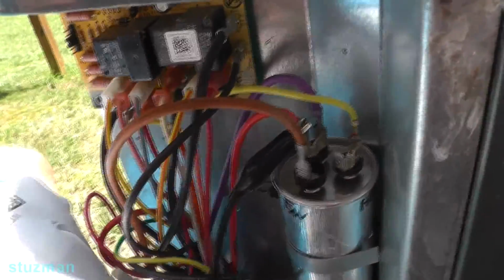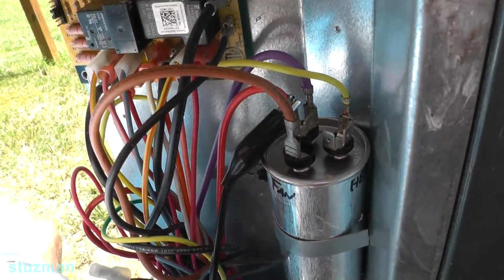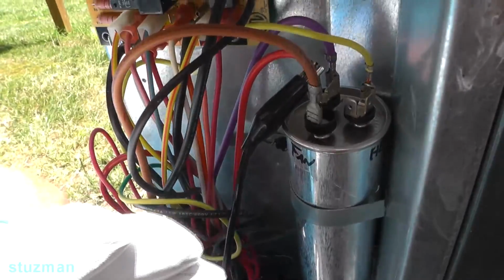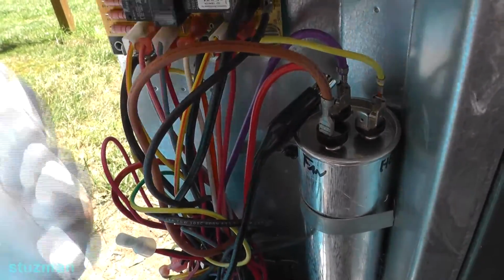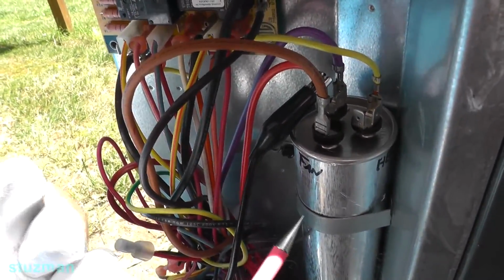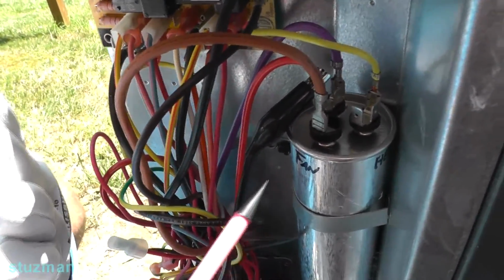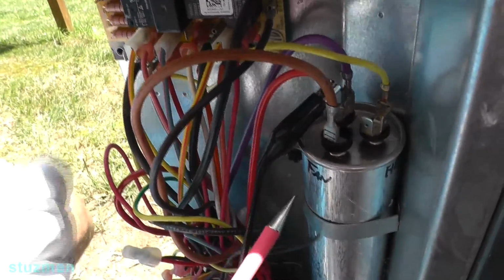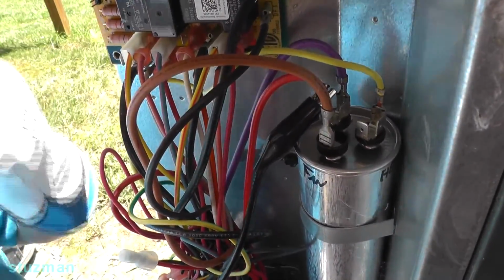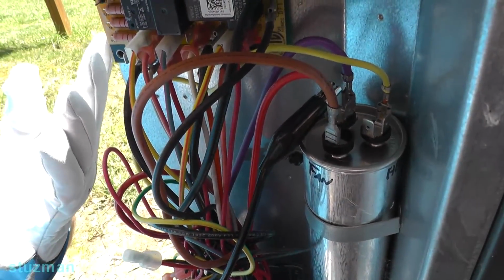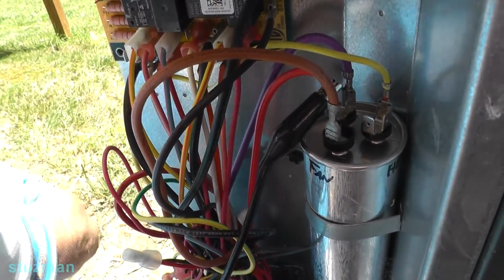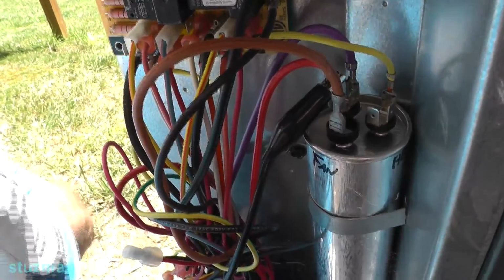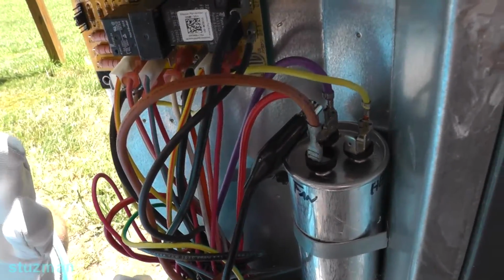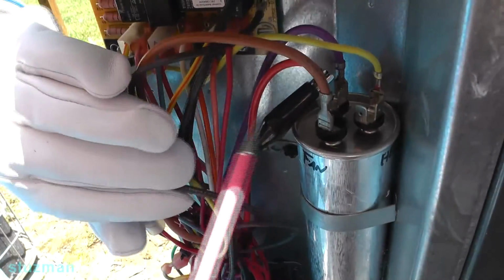So I'm going to take this lead, I'm going to hook it up onto the common terminal. So we got it on the common terminal, and now what we're going to do is discharge this capacitor if there's any voltage on either one of these two capacitors. Now more than likely there's not going to be anything on here because we have our start winding, so when the unit is powered off then the capacitor can discharge through the start windings. However, if you have an open winding, say for the start winding, then this capacitor can still be charged up. So always assume that everything has voltage on it until we get this thing discharged.